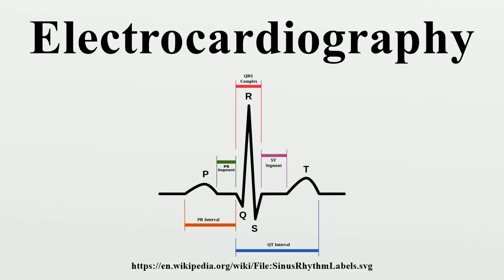An EKG tracing is affected by patient motion. Some rhythmic motions can create the illusion of cardiac dysrhythmia. Artifacts are distorted signals caused by secondary internal or external sources, such as muscle movement or interference from an electrical device.